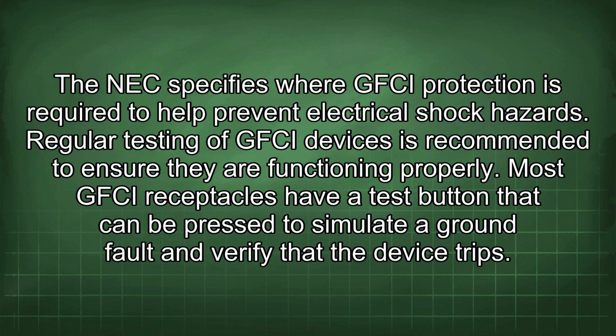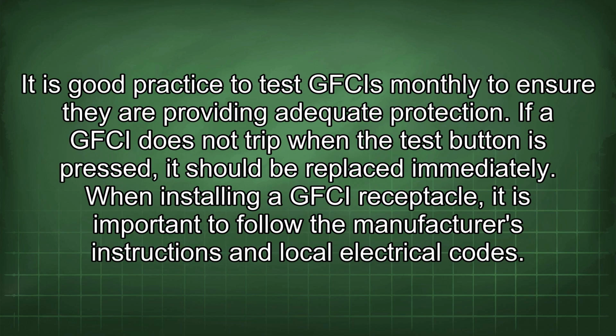Regular testing of GFCI devices is recommended to ensure they are functioning properly. Most GFCI receptacles have a test button that can be pressed to simulate a ground fault and verify that the device trips. It is good practice to test GFCIs monthly to ensure they are providing adequate protection. If a GFCI does not trip when the test button is pressed, it should be replaced immediately.